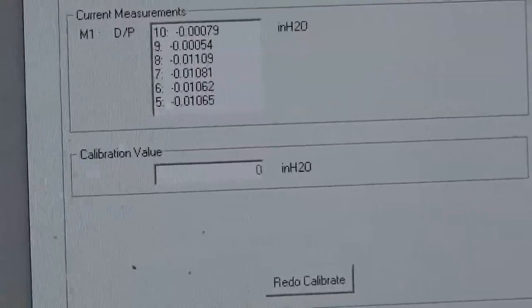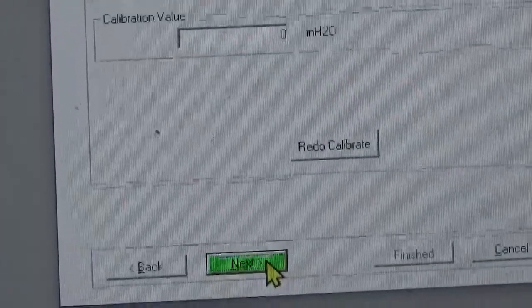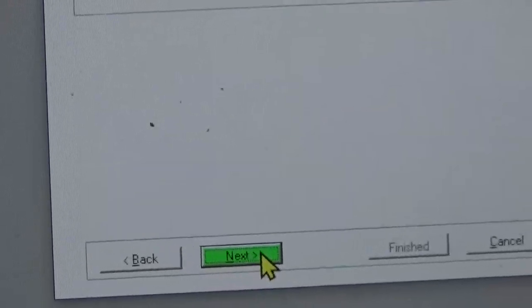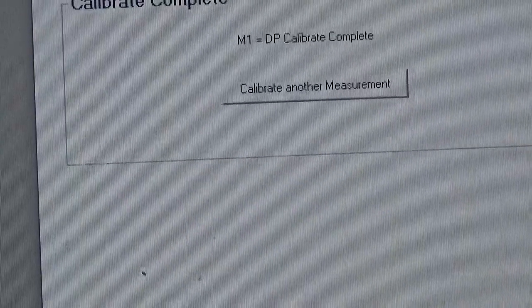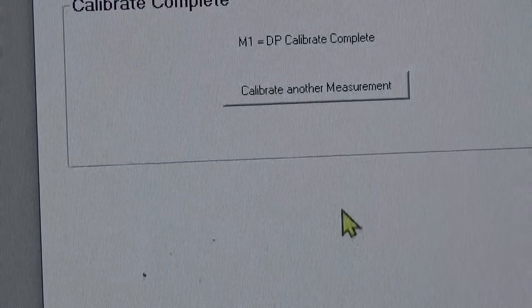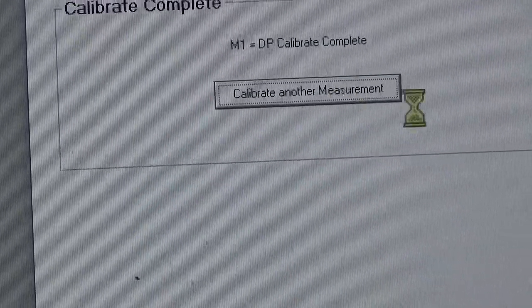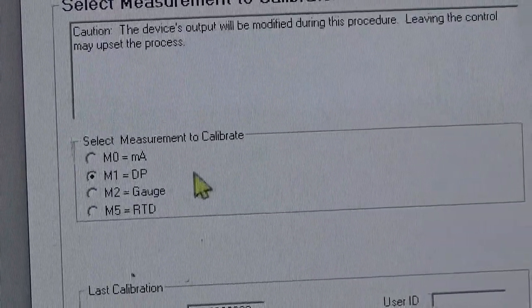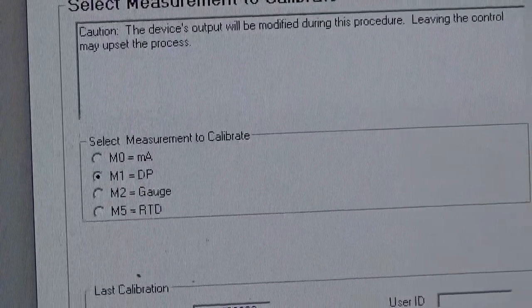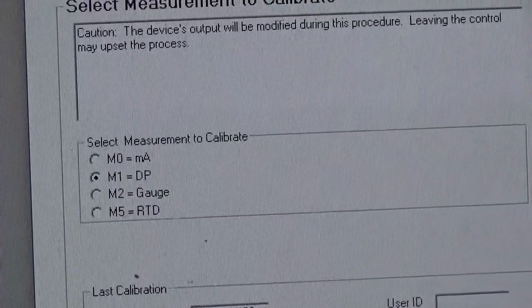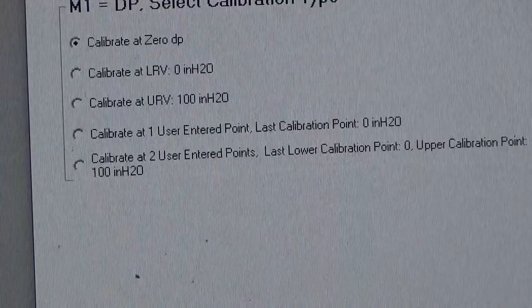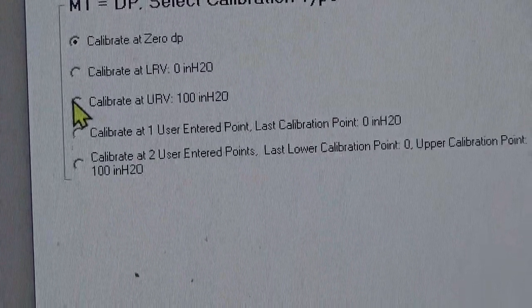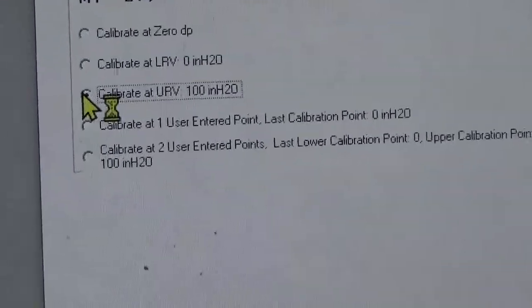And then I'm going to hit the next button. And then it's going to ask me, do I want to calibrate another measurement? And I'm going to say yes, calibrate another measurement. And again, it's going to be DP, but this time I want to do the upper range value because I already did the 0. So I'm going to say calibrate at 100 inches.